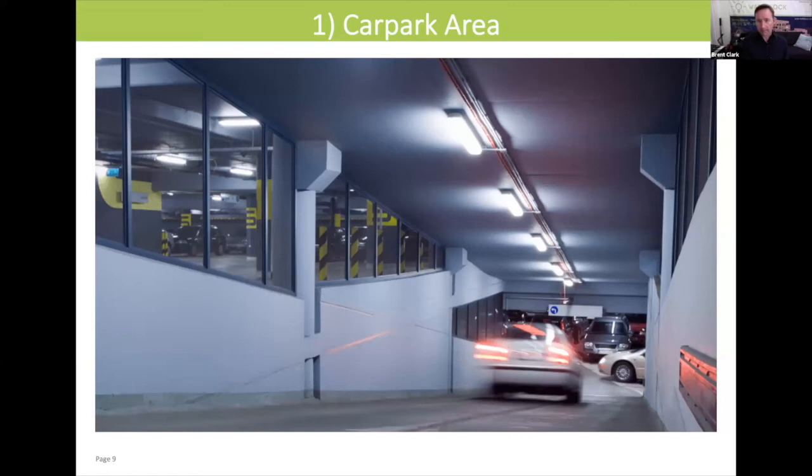So, you know, the other thing to think about is you need a mix of emergency battery backed up lights in a car park area that would meet your 90-minute test if power was dropped to the building. That has to be tested once a year during your annual fire compliance inspection. So you get your fire compliance certificate. And so typically when you're doing the thoroughfares through the car parking space, every second light or maybe every third light will have that emergency battery in it.